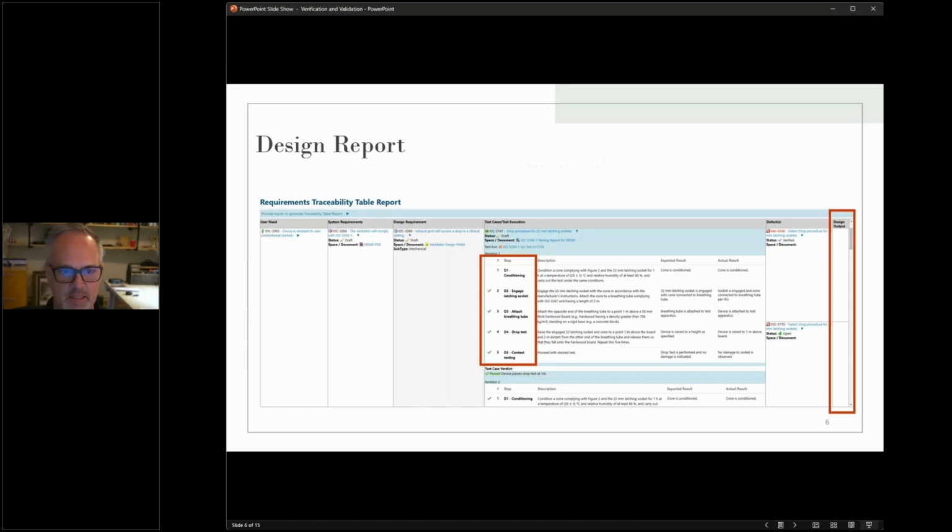And the reason for that is because we want to be able to establish that the DMR or the product that we've approved to shipment and the revision of that DMR has all of the testing that's been done and it's compliant. And without the revision, it's a difficult thing for us to really understand.